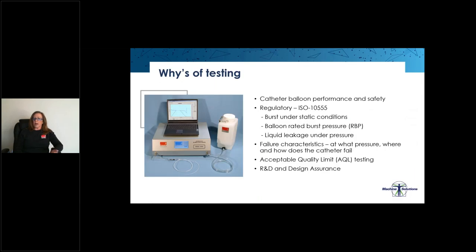First, I'd like to discuss why we do testing. Testing provides us with valuable information about our catheter balloon's performance, as well as its safety for use in the field. Testing is also required for regulatory compliance. ISO 10555 specifies a variety of ways in which intravascular catheters need to be tested for use in the field. Testing allows us to determine the failure characteristics of our products. It's important to know at what pressure the balloon or catheter fails, and where and how does the catheter fail.